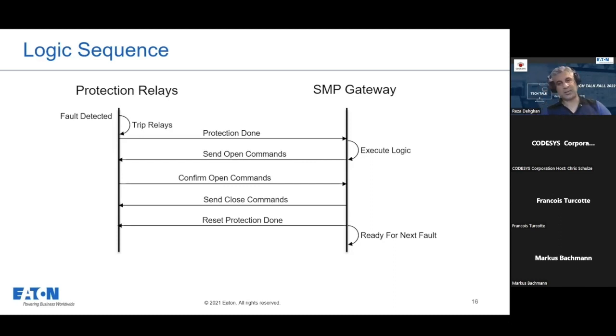Actually, this diagram, I think I'm missing something here, because this is something that we changed almost at the end of the project. At the beginning, we were not waiting for the confirmation of close commands, but we ran into some problems. So we had to add this confirmation of the close commands too. Anyway, after sending the close commands, the way the logic works right now is it waits for the confirmation of the close commands, and then it resets the protection done. Basically, it tells the protection system that everything is done. We are ready for the next fault.